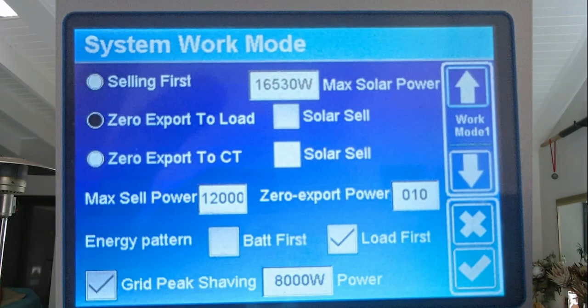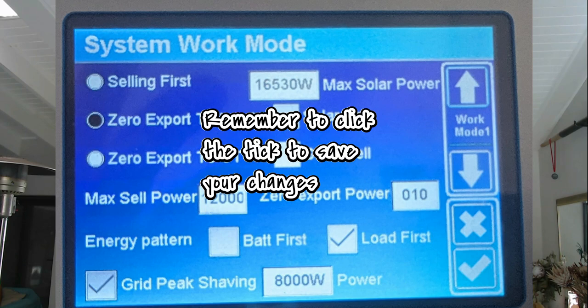This is very easy to enable. You need to make sure your CT coil is connected, because this will be taking control of the amount of power coming in from the grid and restricting that. On the Deye inverter, you'll access this from your System Work Mode screen — go to Settings > System Work Mode, tick the grid peak shaving box, and put in how much power you want to restrict it to.